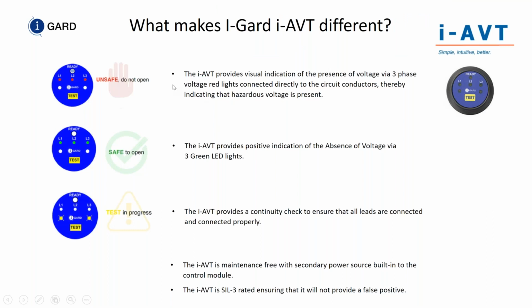So we have the absence of voltage indicator. Three red LEDs means it's unsafe, do not open. Three green LEDs means it's safe to enter that gear. And two flashing yellow LEDs means the test is in process. Do not enter the gear if you do not see 3 green LEDs.